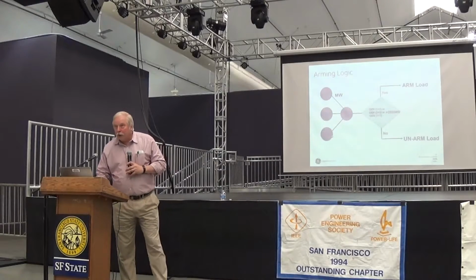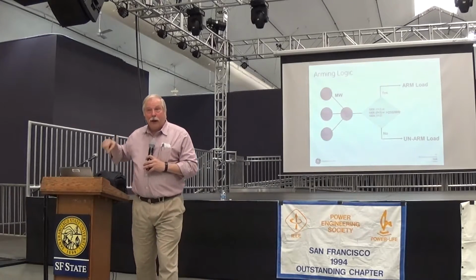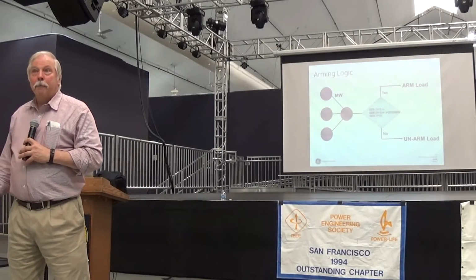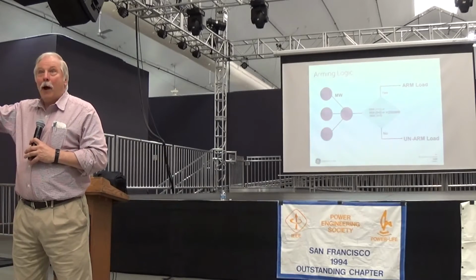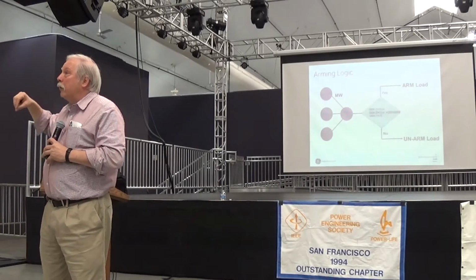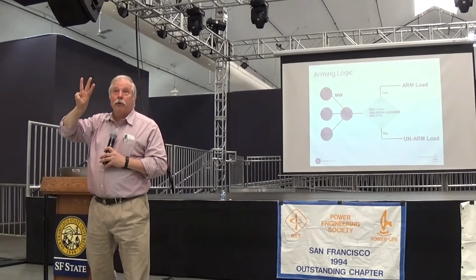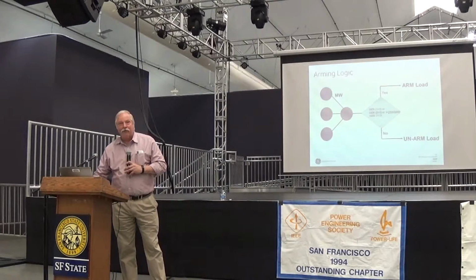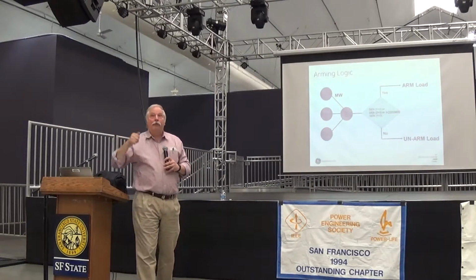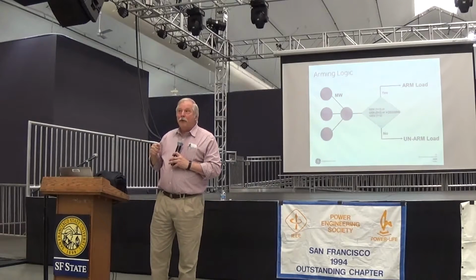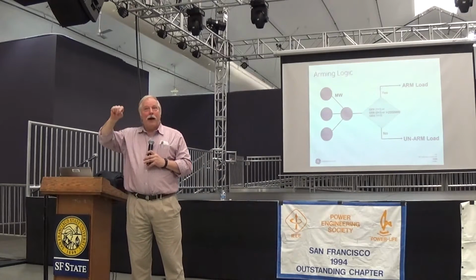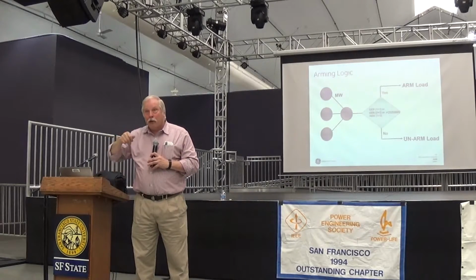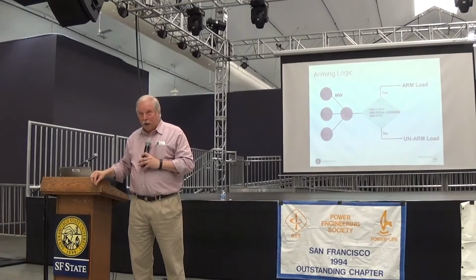So a system was put in, and this has been in service now for almost 10 years at Palo Verde, and they measure the output power from all 3 Palo Verde units, and if 2 of the 3 outputs sum to 2550 megawatts, it arms the system. Arming the system says, identify loads in downtown Phoenix that can be shed on loss of the 2 Palo Verde units.